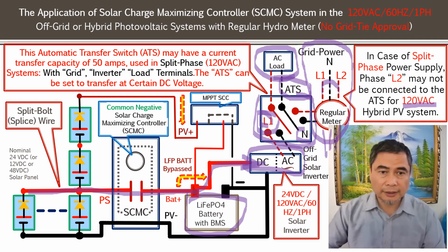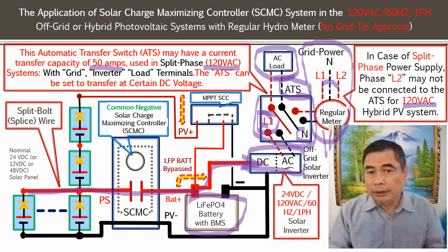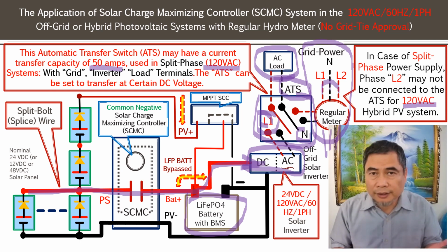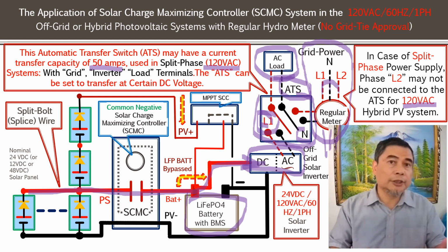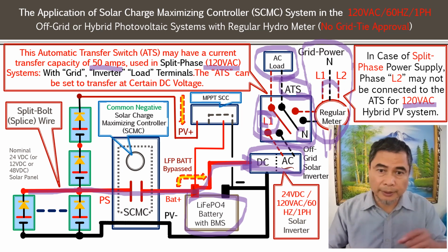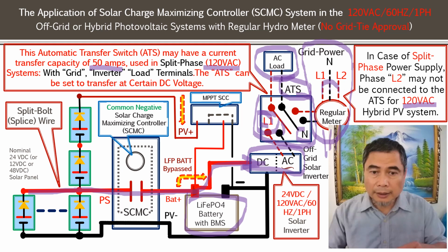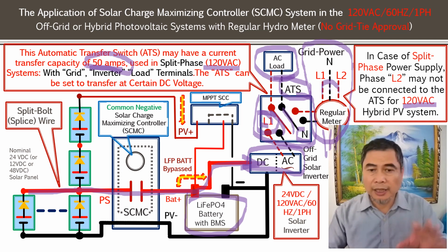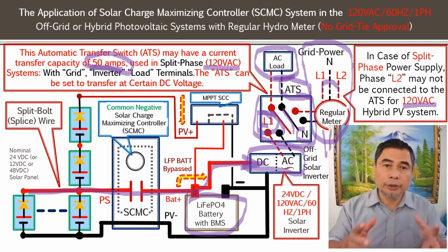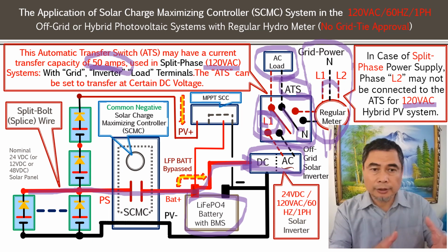So this is a system like 120 volt, 50 amps, can support like a 6 kilowatts, right? 5 kilowatt, 6 kilowatt system. So for 220 system, it can actually support like a 10 kilowatt system because the contact in the automatic transfer switch, they are rated 50 amps. So this is how much it can support, and then you know how to size that solar array properly.